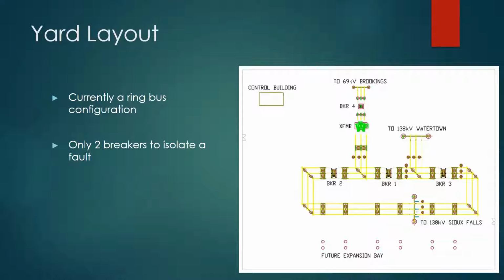The breaker and a half configuration is a lot more flexible than a ring bus in the sense that it's a lot more reliable. And we only need 2 breakers to isolate a fault. And if 2 breakers open, we won't have any other lines being affected. So using this layout, we can fulfill our 2 specifications. Along with that, in the middle of our current ring bus, there is a drive path that is wide enough for a vehicle to drive through. So if anyone needs to service any equipment, they will be able to drive a vehicle through that section.